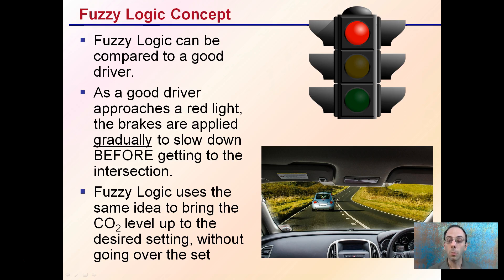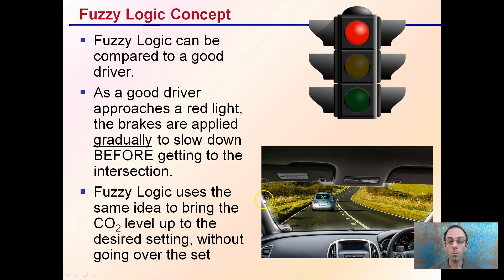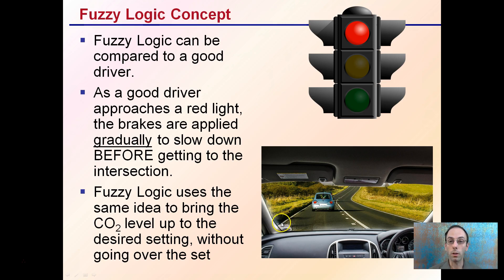The fuzzy logic concept can also be compared to a good driver. A good driver approaching a red light will apply the brakes gradually to slow down before reaching the intersection. Fuzzy logic uses the same idea to bring CO2 levels up to the desired setting without going over. With a standard controller, the brakes would be either fully on or fully off — just one option or the other. Fuzzy logic allows for greater, gradual control over the situation versus simply on or off.